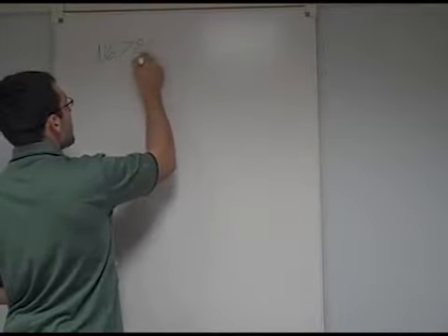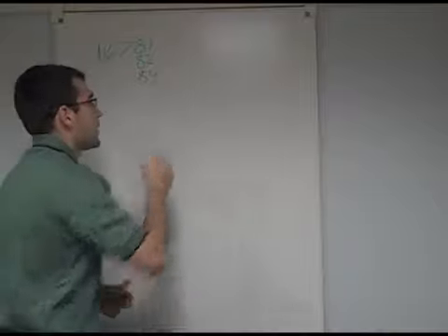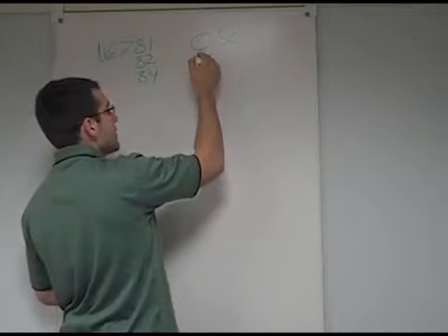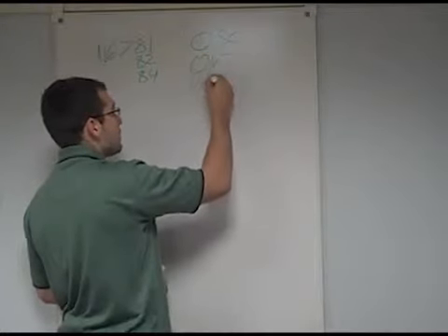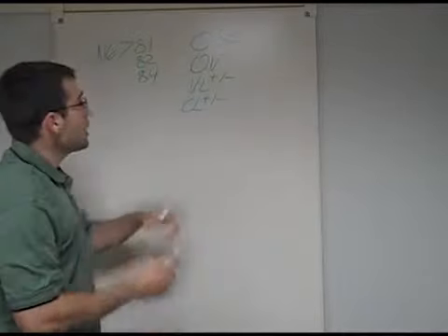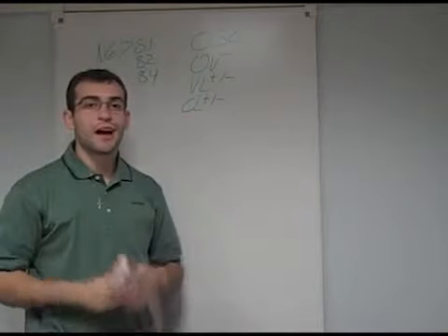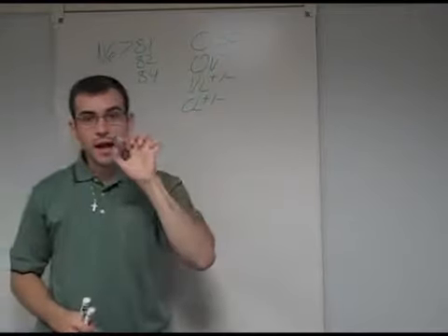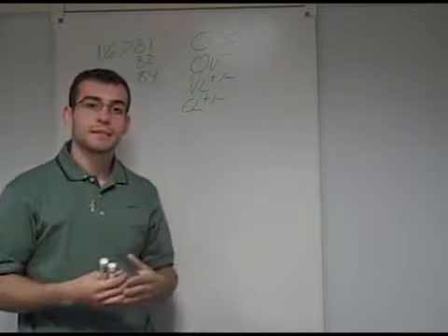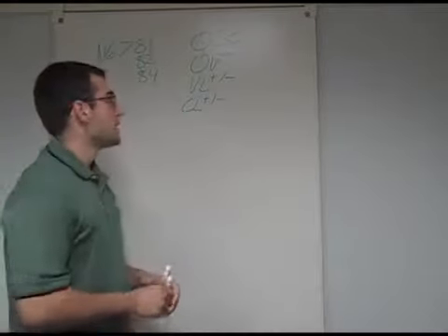So we will first look at the N6781, 82, and 84. These modules have the OSC protection, the OV minus protection, VL plus and minus, and CL plus and minus. The OSC protection stands for the oscillation protection setting. So if the output has an oscillation on it, the power supply detects this and turns off the output in order to save or protect the power supply and the DUT.